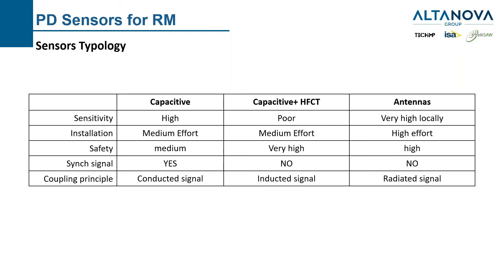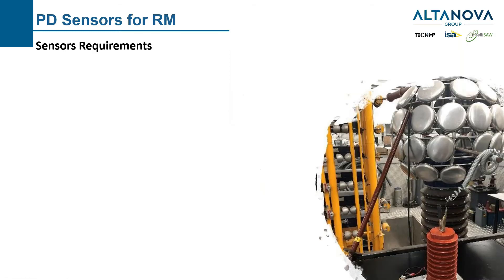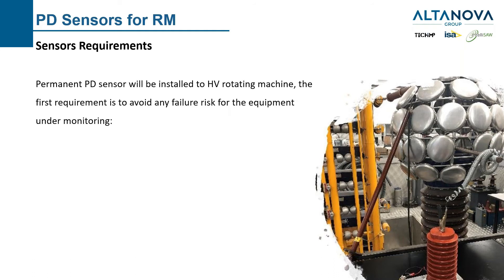One very important topic from my point of view as a testing engineer is the synchronization signal. As mentioned earlier, we build PD data in the PRPD pattern. In order to have phase resolution, we need a synchronization signal that is directly correlated to the applied voltage to the insulation. This signal is made available with capacitive couplers, but we don't have such a signal when using capacitive sensors plus an HFCT, or with antennas. The coupling principle is: conducted signal for capacitive sensors, inducted signal for capacitive sensors with a high frequency current transformer, and radiated signal with antennas.